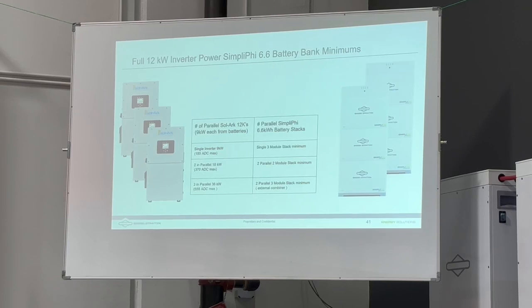I can't take a single one of these 6.6s and run a 15K full bore out of it. The battery will communicate with the inverter and tell it not to anyway, but you have to size your system appropriately - not just for how long an outage you want to survive, but also for the maximum amount of power you're going to pull out at one moment.